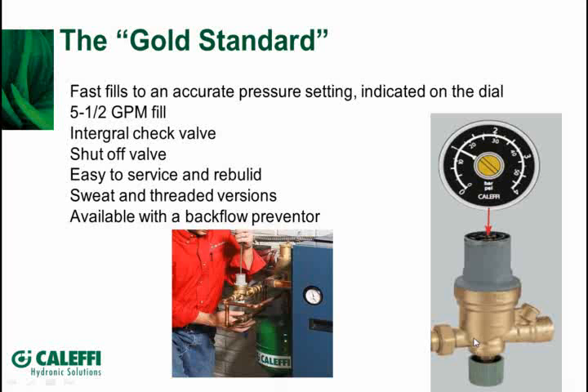The other thing about this valve, it's a very fast filling valve. It'll fill up to about 5.5 gallons a minute, as long as you have about 30 pounds pressure or more coming into this side of it from your water system in your house or in your building. So it's a very fast filling valve. We also put a check valve in there on the discharge side, right in here. It doesn't pass code for a backflow preventer, but it is another level of protection to keep the fluid from backing out of your system into your water.